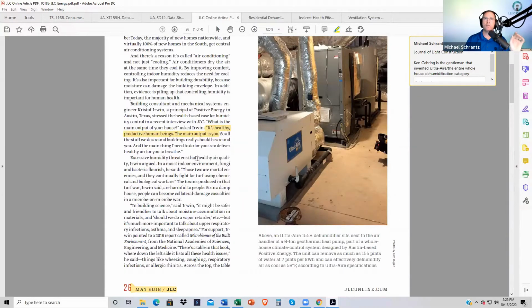One of the things we talk about is overcooling, and this issue of whether it's the software that helps companies size the equipment - which has a margin of error and might oversize what's needed - or the HVAC contractor who says it's calling for 2.6 tons so I'll add a 3-ton, and then it's oversized further. What ends up happening, and you've done a fantastic job explaining this, is you satisfy the temperature very quickly, but you don't have the run time to even have the evaporator coil remove some percentage of the moisture.